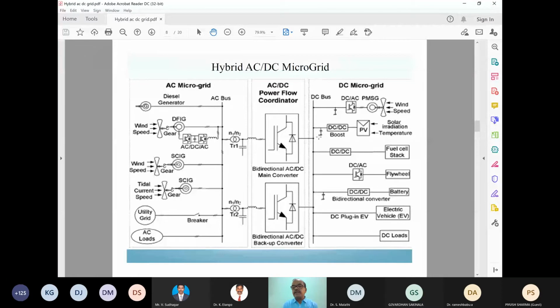Most non-traditional kinds of generation produce only real power. To run the system, you also require reactive power, and for that you use a power electronic device. This is a very important message, because the system is complex, involving both real and reactive power. Real power is directly proportional to current, reactive power is directly proportional to voltage, and to run the system you require both voltage and current.